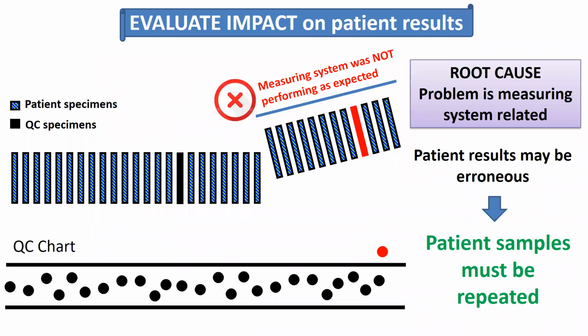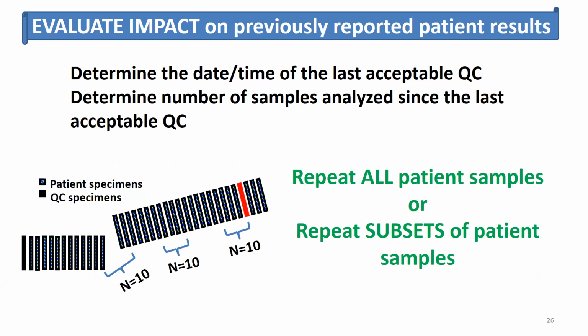The root cause of our glucose QC failure was a leaking pump seal. Because the analytical measurement system was not performing as expected, we don't know when the problem started, so we need to repeat previously analyzed patient samples. One approach is to repeat all patient samples between the time the QC failure was detected and the time of the last acceptable QC, when we know the analytical measurement system was performing as expected.